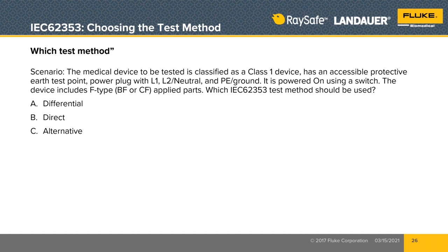All right, so another little poll question here. Which test method? The medical device to be tested is classified as a class 1 device. It has an accessible protective earth test point. It has a power plug with L1, L2, and protective earth. It is powered on using a switch. The device includes F-type patient connections. And which IEC 62353 test method should you use? A, differential, B, direct, or C, alternative?